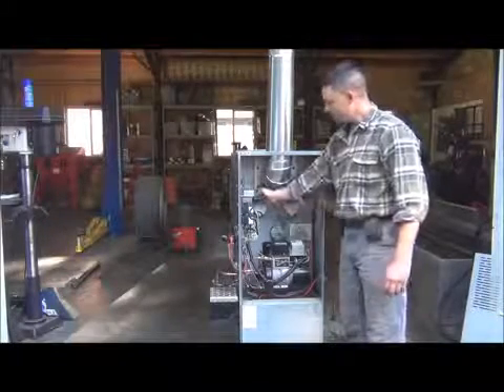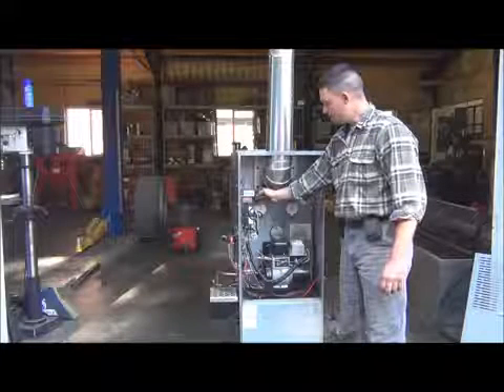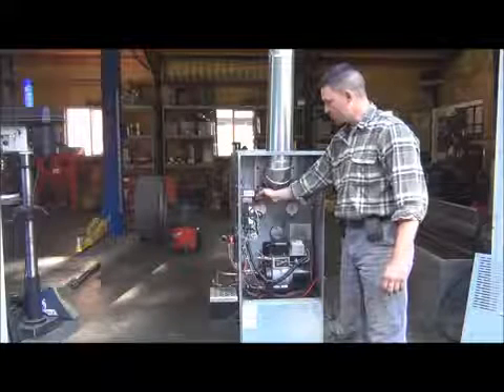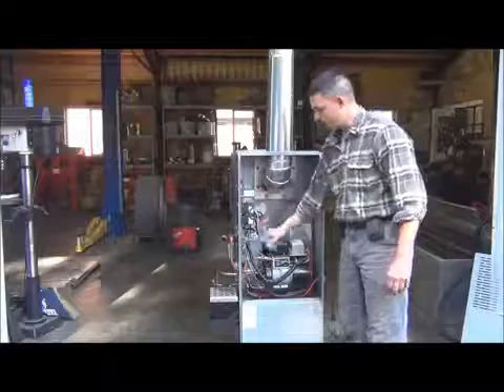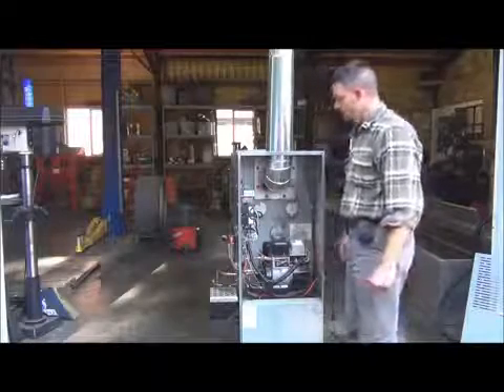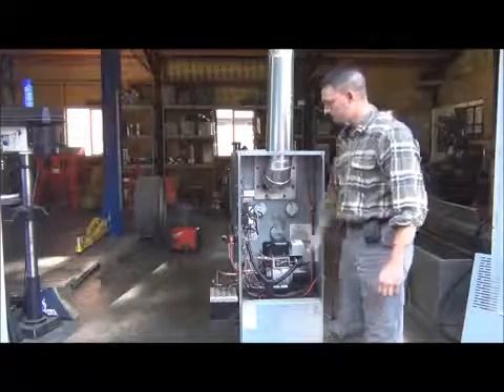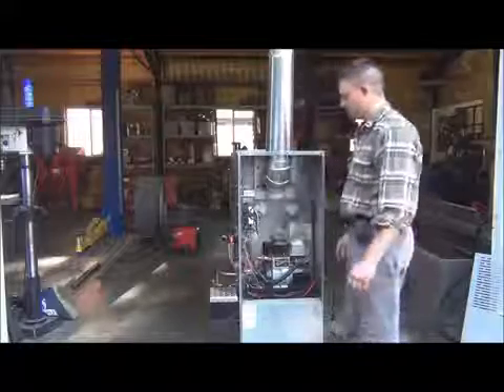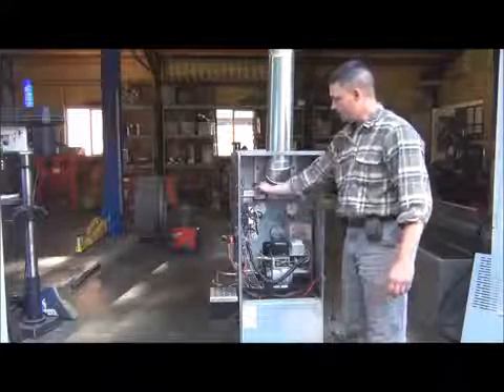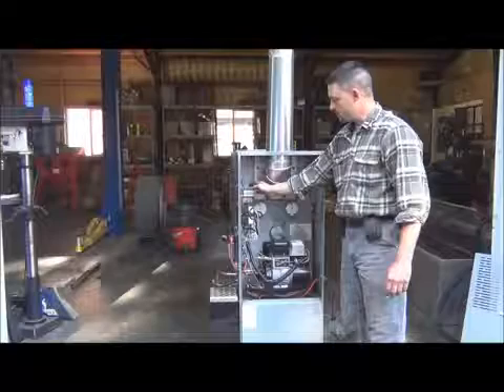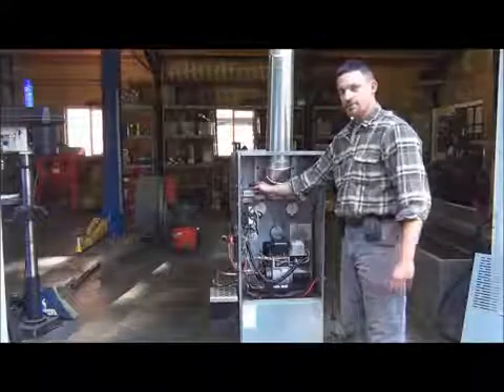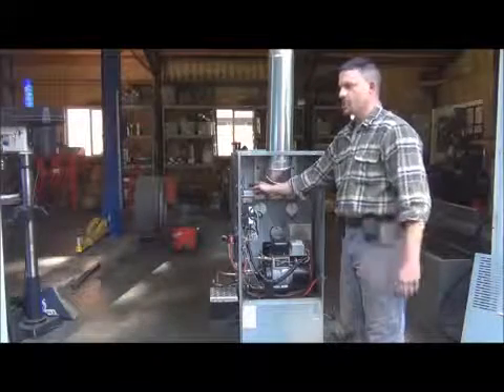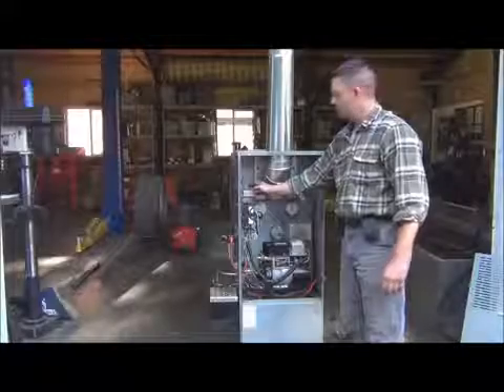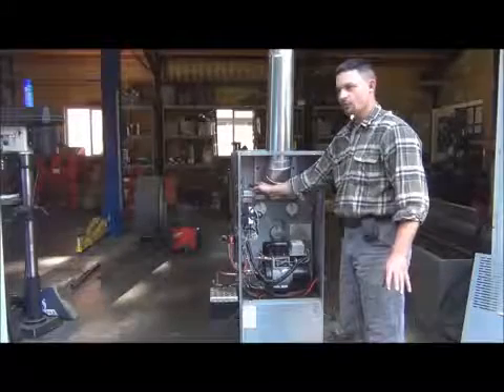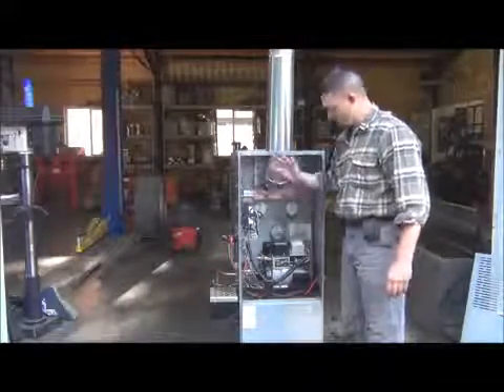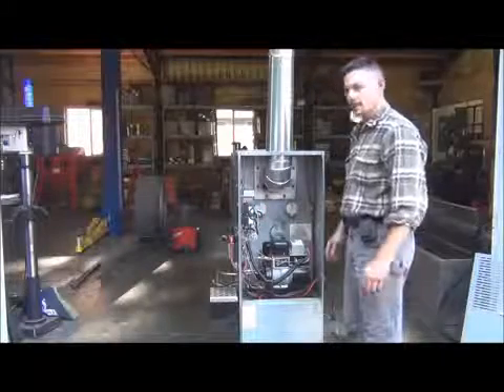I have my time delay relay right here, and this gives my 20-second maximum run time for the oil pump that pumps oil up into my siphon tank. And if this is timed out, the only way to reset it is to hit the red reset button on the outside. And then I have my main power relay, and this just takes an input from the thermostat.